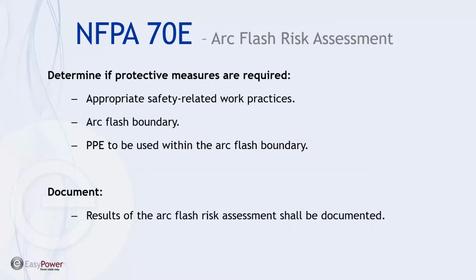Now, as was mentioned earlier, there are a couple of ways to determine arc flash boundary and PPE: with a lookup table, and then there's also the incident energy calculation method. Obviously, that's what I'm focused on. The bottom line is to determine the appropriate safety-related work practices required for the equipment, the arc flash boundary, and then the PPE used within the arc flash boundary. And this must be documented as a result of the study.